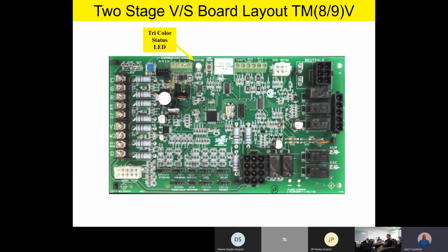Now, it should be noted, if you have any faults on the control board, you can retrieve those faults by pushing a last error button, which we'll show you in just a second. But please remember that it's going to remember the last 5 faults, the most current 5 faults. So if you have 8 faults on the board, for instance, it just remembers the last 5 for you. And then to reset that board, if you hold that last error button down for about 10 seconds, it'll reset that memory. And that's just good practice, fellas. If you get out on a field call and you've got some errors on the board, clear those errors up before you leave the job site is what I typically do or recommend. So be sure and hold that last error button down when you're done servicing the product and clear that memory so that you'll always have the freshest faults on there if you happen to have faults.